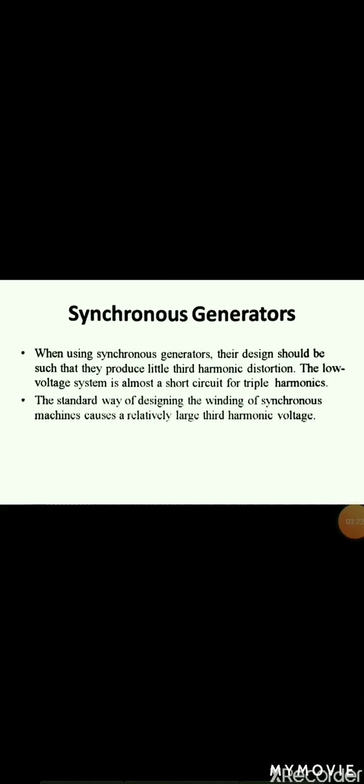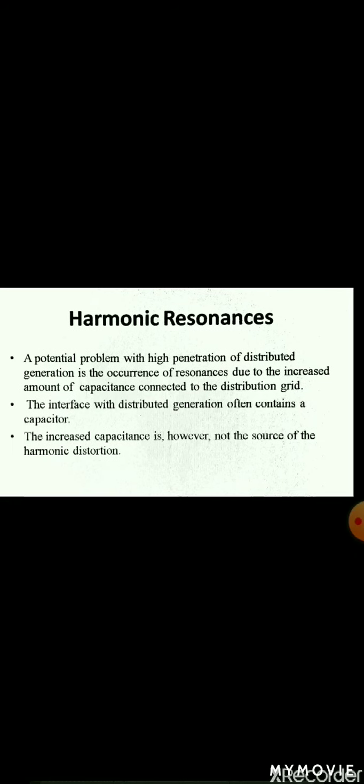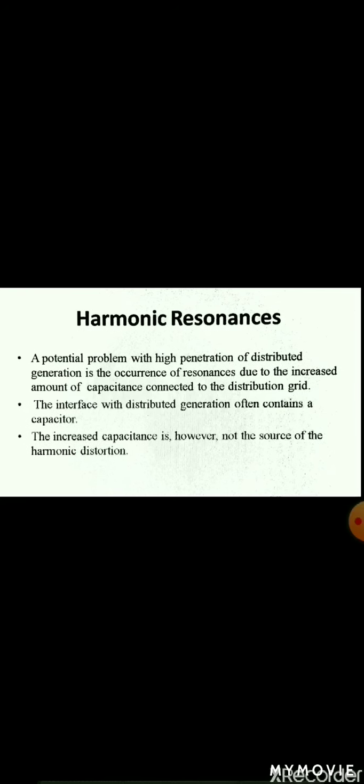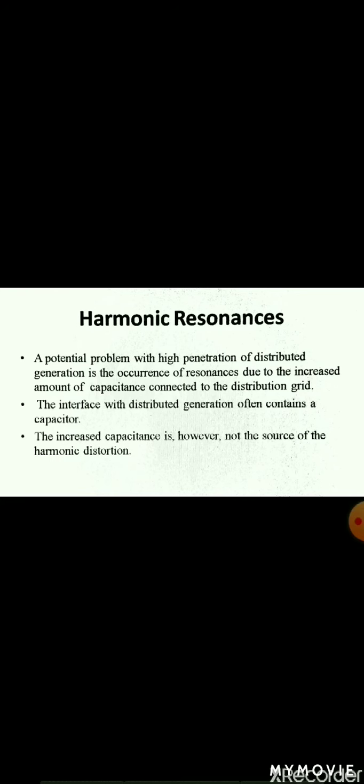Next is synchronous generator. When using synchronous generators, their design should be such that they produce little third harmonic distortion. The low voltage system is almost a short circuit for triple harmonics, which could cause a large third harmonic current with standard synchronous generators. The standard way of designing the winding of synchronous generators causes a large third harmonic voltage, about 10% of the fundamental component, whereas the 5th and 7th harmonic voltages will be around 1%. As the third harmonic component has zero sequence character, it is not transferred through delta connected generator transformer.